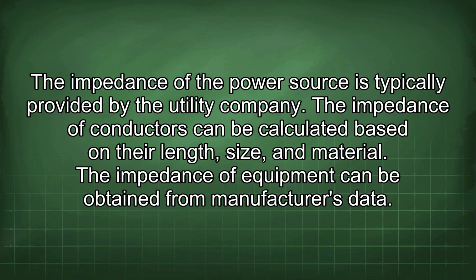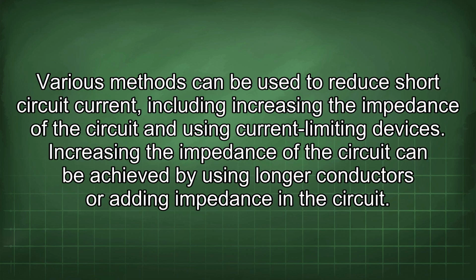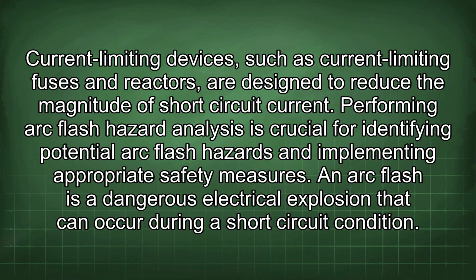The impedance of conductors can be calculated based on their length, size, and material. The impedance of equipment can be obtained from manufacturer's data. Various methods can be used to reduce short-circuit current, including increasing the impedance of the circuit and using current-limiting devices. Increasing the impedance of the circuit can be achieved by using longer conductors or adding impedance in the circuit. Current-limiting devices, such as current-limiting fuses and reactors, are designed to reduce the magnitude of short-circuit current.